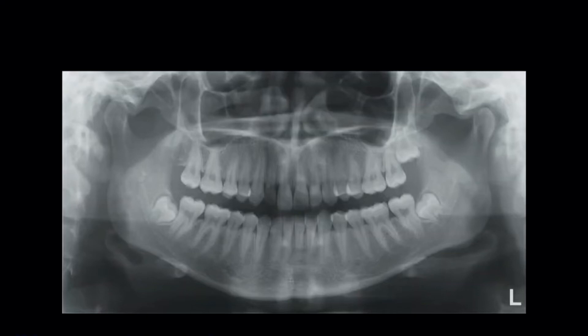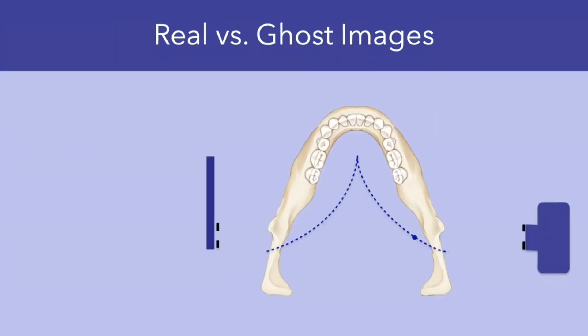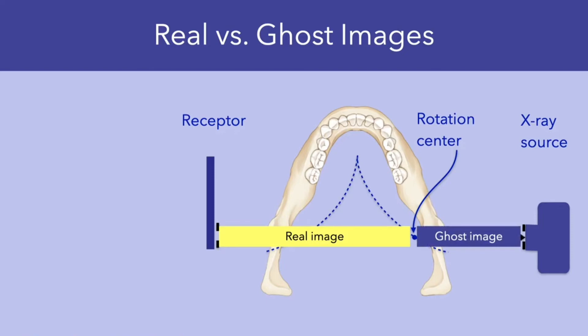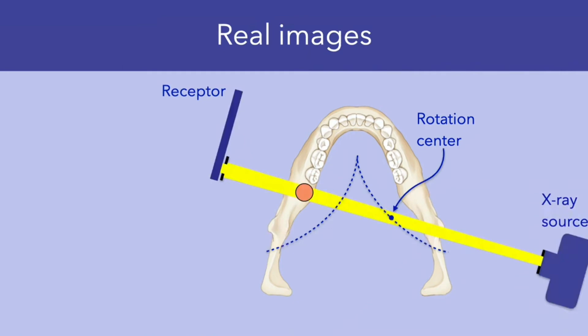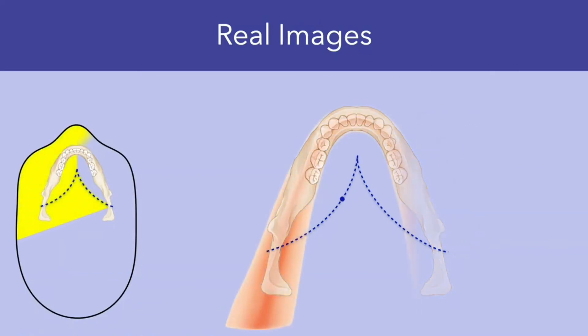Based on the projection geometry, there are three broad categories of images to consider: real images, double images, and ghost images. The first distinction is between real and ghost images, and this distinction is based on the position of the object relative to the X-ray source, the rotation center, and the receptor. Objects located between the rotation center and the receptor cast real images, whereas the images of objects between the rotation center and the X-ray source are referred to as ghost images. When projecting real images, only those structures located within the image layer will cast sharp images, whereas real images of structures outside the image layer will be less sharp. This graphic demonstrates the anatomic zone of structures that will be projected as real images, and again only those structures within the image layer will cast sharp images.